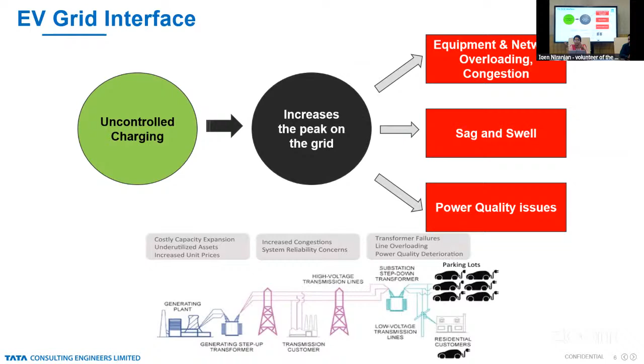So okay, let us take a small analysis. A car battery of 30 kilowatt hour, charging, let's assume, because maybe we won't charge 100%, it's just a top-up charge. So let's assume 60%, which is 18 kilowatt hour. Normally in summer a 2 BHK residence consumes around 10 to 12 kilowatt hour a day, but when you're charging a vehicle, it's almost 1.5 times more. Consider normally a 500 kVA transformer is a distribution transformer feeding 80 houses. So if 20% of the houses add EVs and charge at peak demand, the load increases by 60 kVA. This impacts the transformer: the 500 kVA transformer gets overloaded by 12%.